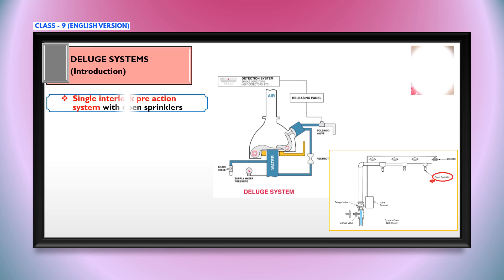Deluge systems are similar to single interlock type pre-action systems. However, the biggest difference is that deluge systems use open sprinklers or nozzles. In this deluge type, open sprinklers or nozzles are connected to the piping network. These systems also have integrated detection systems with a releasing panel similar to the pre-action systems.